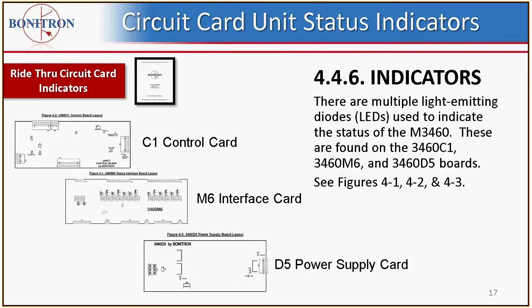And that's basic functionality. In the next session, I'm going to get a little more detailed and provide some signal tracing. But for right now, we're just talking about indicators and how to visually inspect the ride-through to determine unit state of health. Inside the M3460s, there are 3 major boards that have LEDs that allow you to observe unit state of health, if you have a fault indication, or if you're just doing a quick check. Usually these are open chassis units and the LEDs are visible, but you would have to open the cabinet to get in and look at the actual circuit cards on the open chassis 3460.